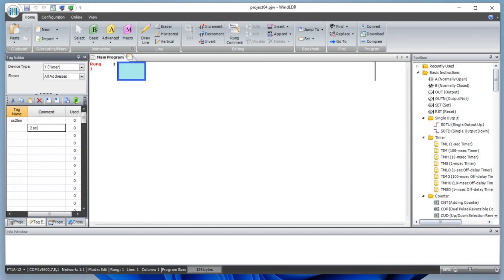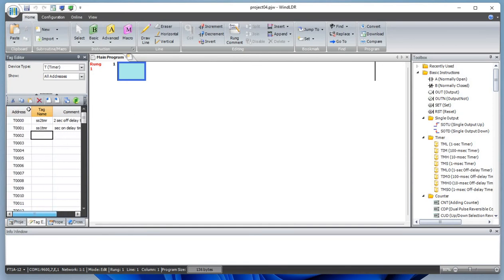Let's define some timers. We have a two-second timer — note you cannot start a variable name with a number, so we'll call it 'ss2tmr'. This one is a two-second off-delay timer. And let's define this as a one-second on-delay timer called 'ss1_tmr'. So two timer registers, T0 and T1, are defined.